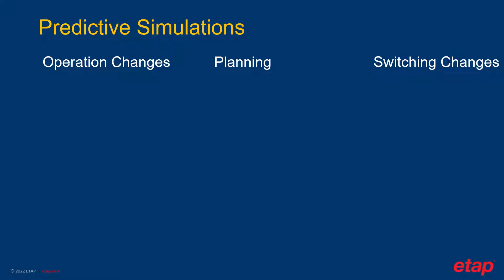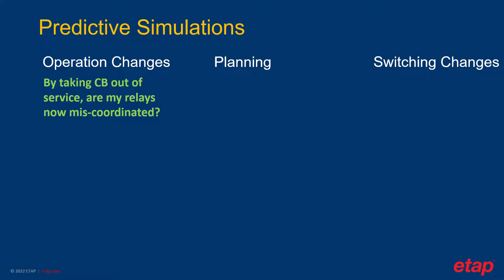Let's take a look at 3 common scenarios where you can use online simulation in areas of operation, planning, and switching changes. In operations, we can evaluate changes such as taking a critical circuit breaker out of service for maintenance reasons. Therefore, we need to know things like how will it affect my relay coordination. For planning, we can evaluate what is the effect of increasing the load. This could be because operations suddenly requires to increase the loads to a substation due to the changes in the process, or there is an ongoing expansion or changes in the connected loads as the substation evolves with the operations.